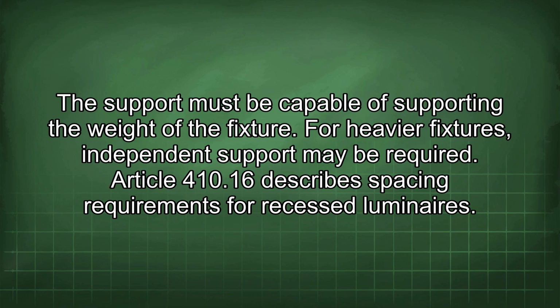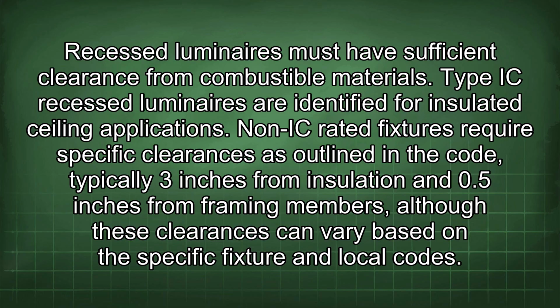Article 410.16 describes spacing requirements for recessed luminaires. Recessed luminaires must have sufficient clearance from combustible materials. Type IC recessed luminaires are identified for insulated ceiling applications. Non-IC rated fixtures require specific clearances as outlined in the code, typically 3 inches from insulation and 0.5 inches from framing members, although these clearances can vary based on the specific fixture and local codes.